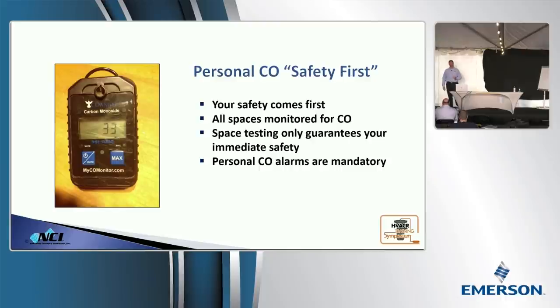There have been a lot of guys that have been drug out of mechanical rooms unconscious because they assumed the air that they were breathing was safe. Even though we're in an open tent, there's vehicles running around, there's generators. A lot of us are staying in hotels. Hotels are the number one most dangerous location for CO poisoning events. So as we talk about combustion air, your safety is number one. Your safety comes first. So monitor the places that you go into. Monitor the air. Now, with space testing, you need to be aware of this.